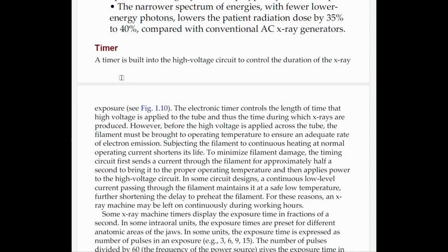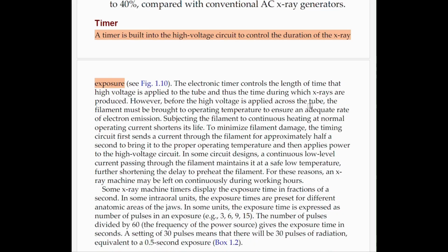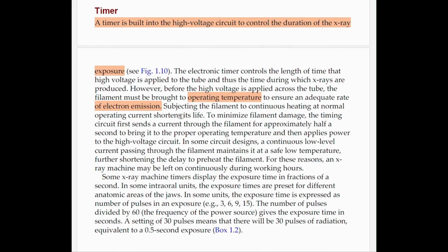Then comes the timer. A timer is built into the high voltage circuit to control the duration of the X-ray exposure. The electronic timer controls the length of time that high voltage is applied to the tube and thus the time during which X-rays are produced. However, before the high voltage is applied across the tube, the filament must be brought to the operating temperature to ensure an adequate rate of electron emission. Subjecting the filament to continuous heating at normal operating current shortens its life.